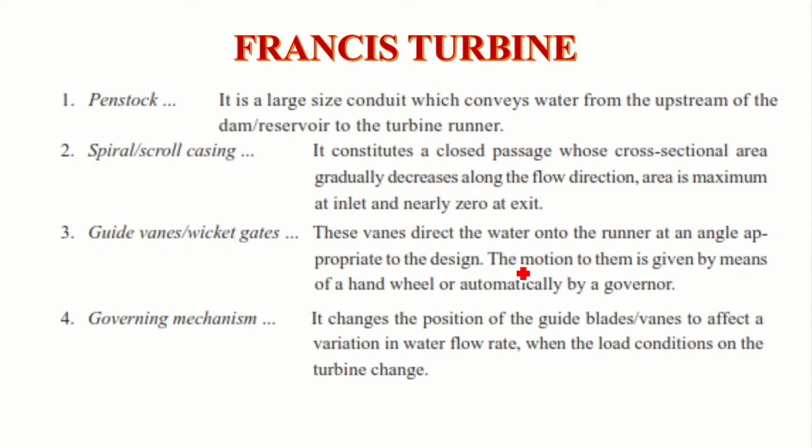So these guide vanes guide water to the runners. Actually, we can adjust the guide vane angles. According to the load, we can adjust the guide vane angles, thereby we can change the direction of water. So it depends upon the load which we need, and by changing the angle, we can change the direction of water.